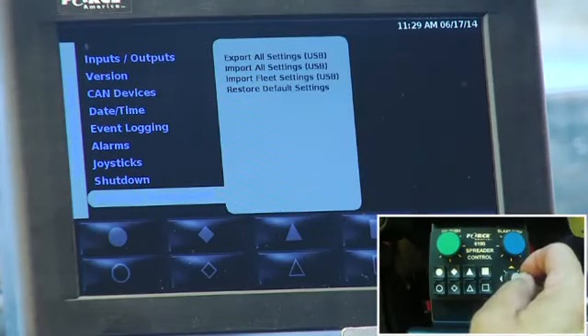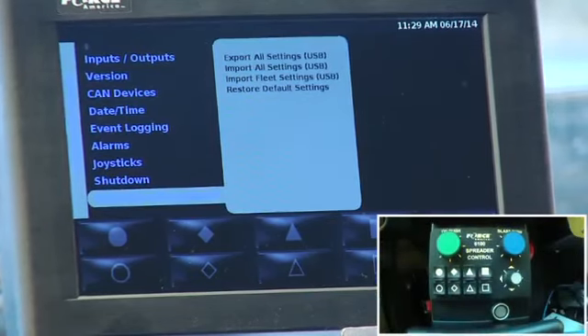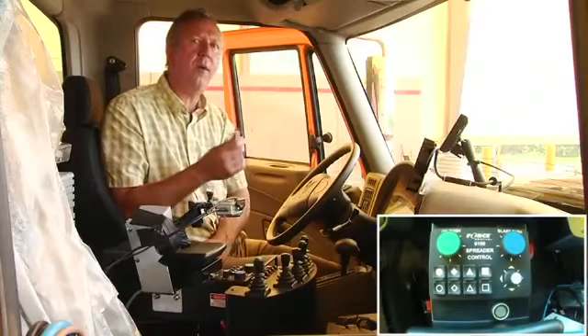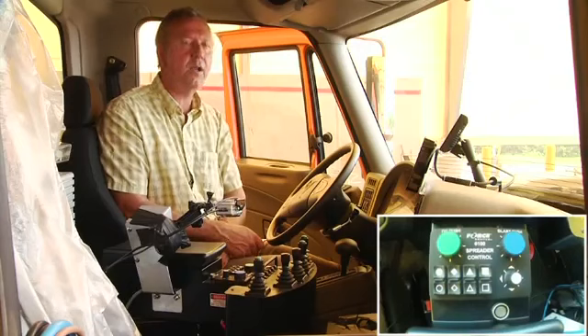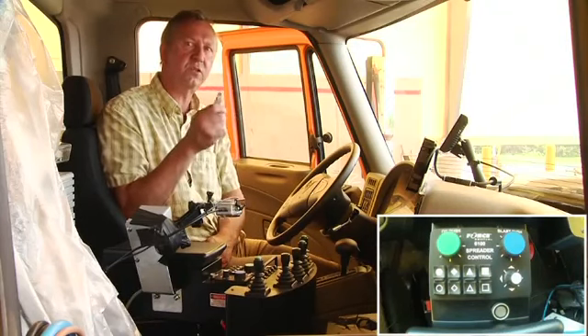So I'm going into setting management, and you see on the screen it says export all settings, import fleet settings, and restore default. When I upgrade the software, I'm going to lose all my calibration settings, and I don't want to do that, so I want to save them onto this thumb drive.